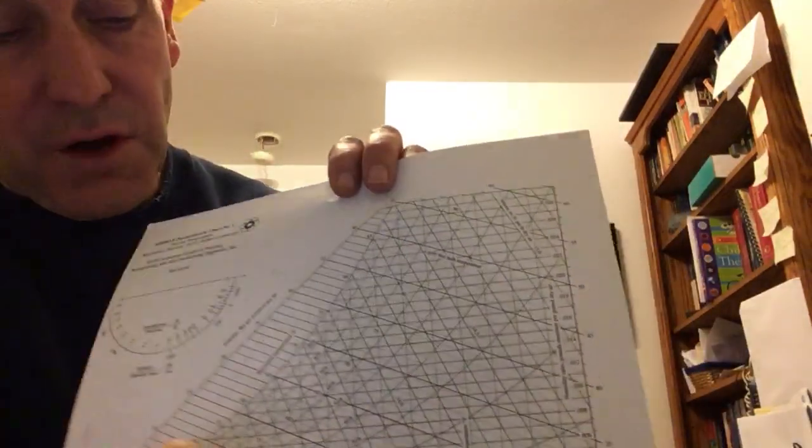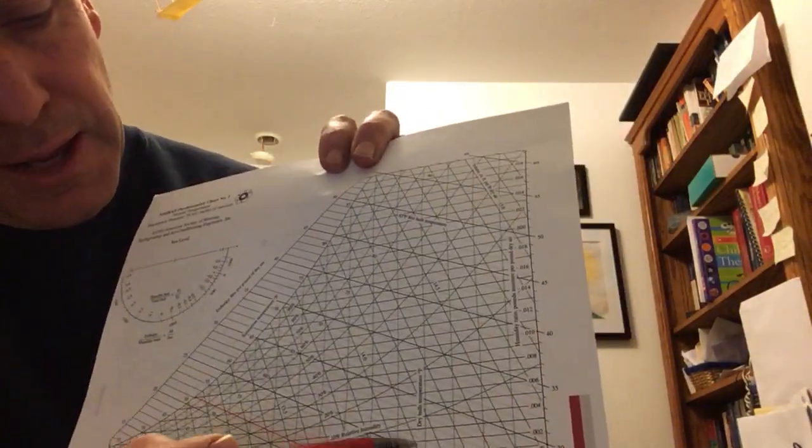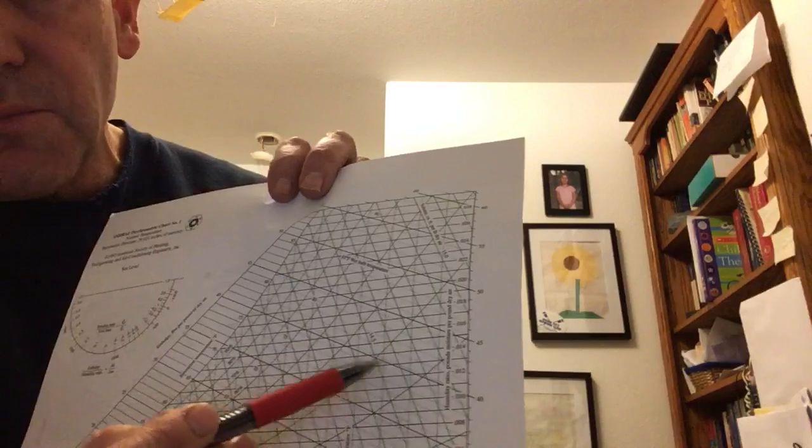Okay, so let's go ahead and get the enthalpy of that air that I was talking about. It's 100 degrees Fahrenheit, 0.008 specific humidity. What you're going to do is first follow up the 100-degree line, and then go across from the 0.008 and plot your point. So go ahead and do that. You can do it lightly in pencil. When you take test 3, if you want to bring a clean psych chart in so that you can mark it up as you read various points, that's just fine.